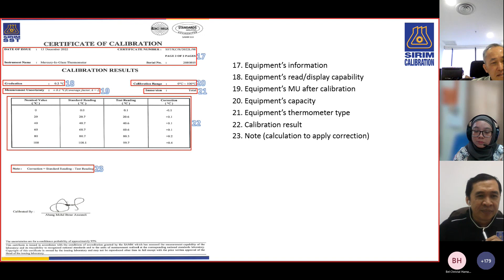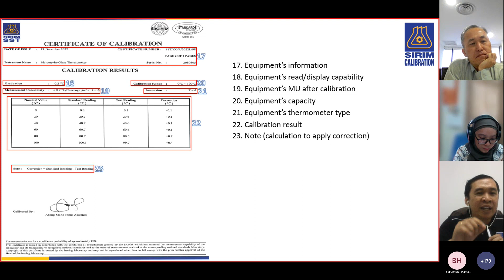So in order for you to get the accurate reading as per the standard reading, the test reading, which is 20.6, must be added with the correction, plus 0.1. So that is your actual reading, and plus the measurement uncertainty, which is 0.2. Okay, so that is your final reading. You understand? So your final reading after doing a correction is 20.7 plus minus 0.2, which is the measurement uncertainty. So always remember that, and I hope you understand that one.